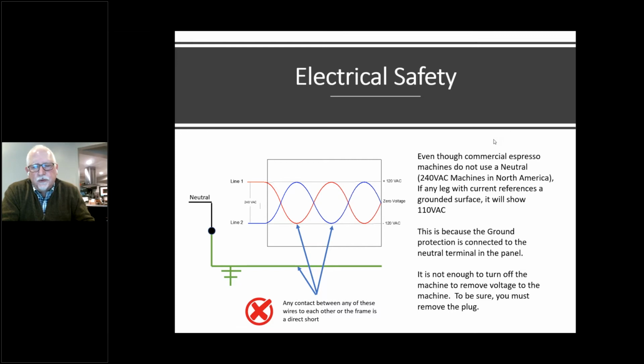The difference is that the neutral wire, because it's carrying a load back from the machine, has to be isolated from everything else, because it's always carrying some degree of current back, because that's the reference for the waveform. The ground wire is a protective shield around that, so that if any of those wires make contact with the ground, it causes a short circuit. Now, if any of those wires were to contact neutral, it would also cause a short circuit. But the neutral is actually something that's used. So by keeping the ground separate, it becomes a safety device.